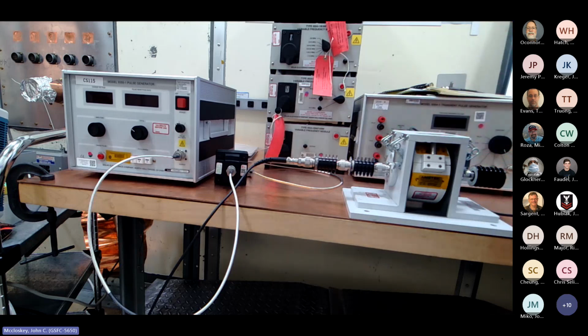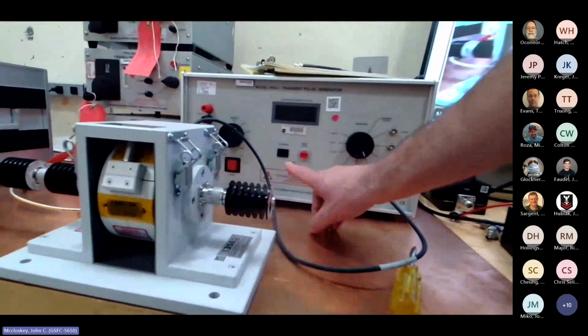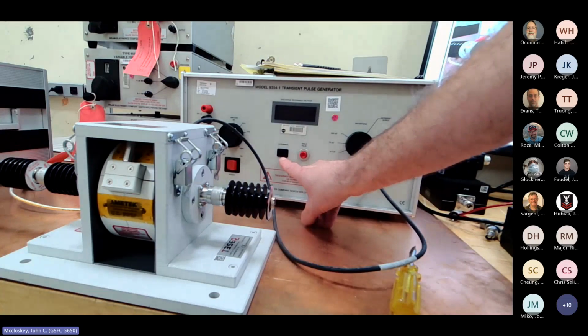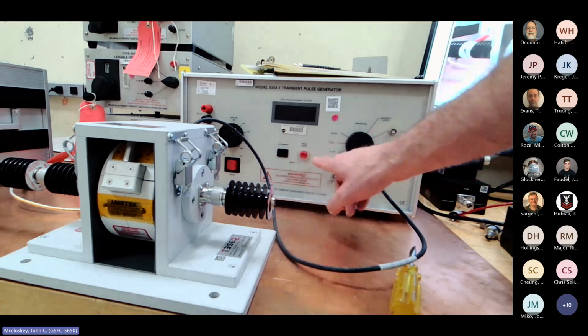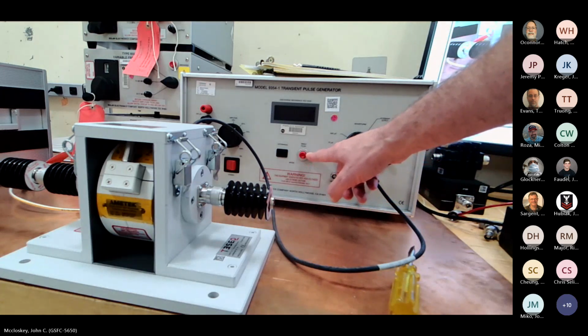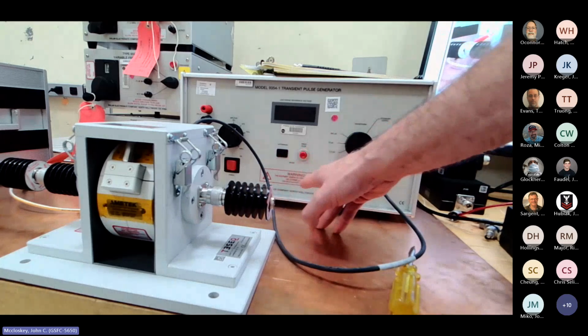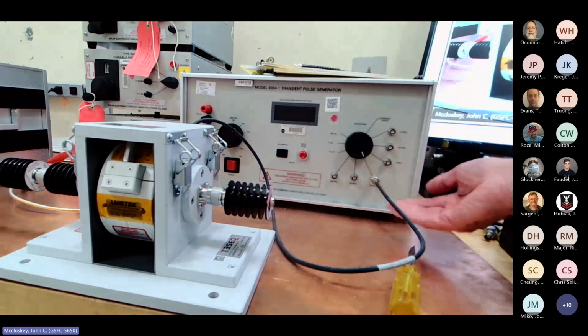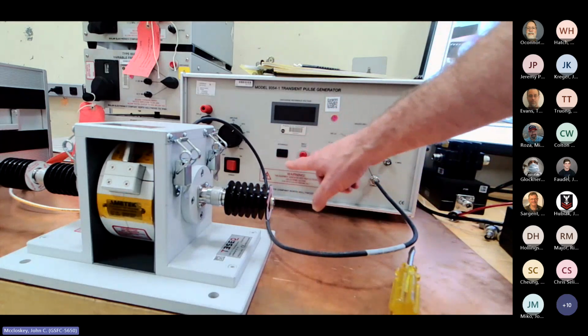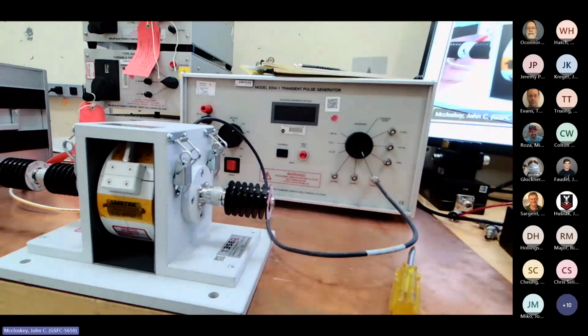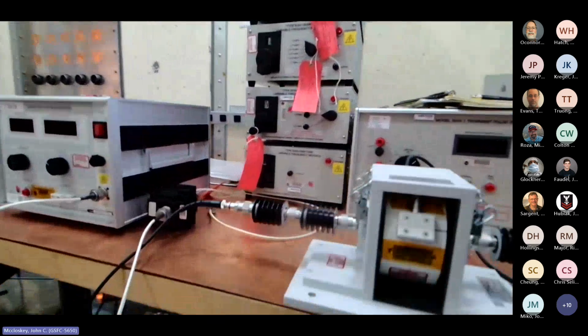Here's the power switch. So this box actually has an enable, or once you turn the power on, then, well, it says automatic or manual, right? It's on the manual setting right now, and then you can hit this button for a single pulse. Oh, I'm sorry. Thank you. Well, there's this automatic manual switch. So when it's on manual, basically the output is disabled until you hit the single pulse button. So I like to turn it on with it in that position, so it acts as an enable switch. That I can turn the unit on, but I'm not getting any signal out of it until I tell it to, either by flipping it over to automatic where it gets a repetitive pulse or it hits single pulse. The 115 generator doesn't really do that. So, I don't think the CS116 generator does either.